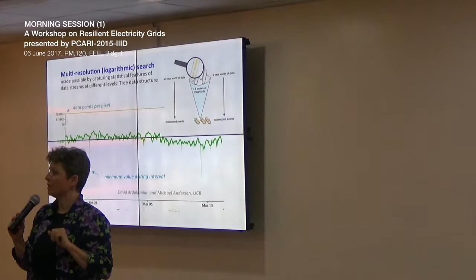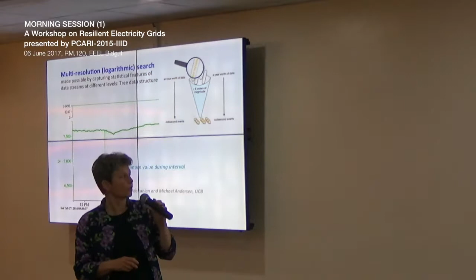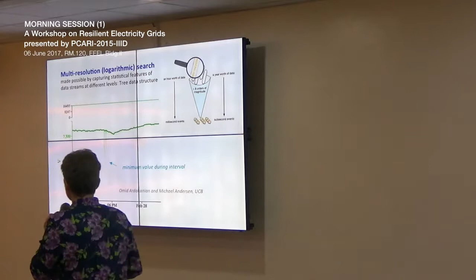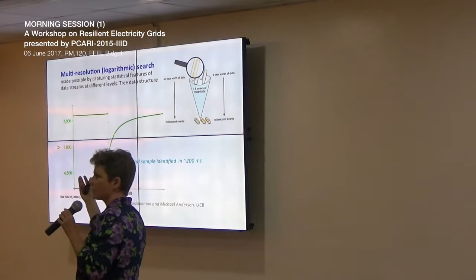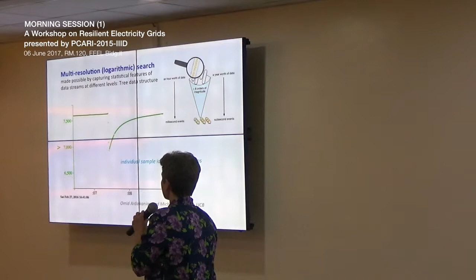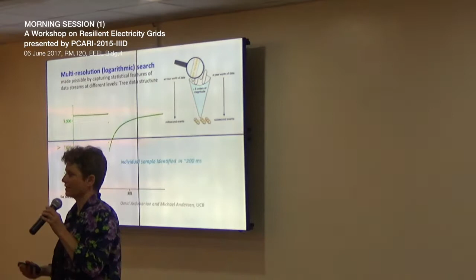We can find voltage sags without digging in too much deeper, but I can then zoom in and say, okay, the voltage sag on February 27th was actually there, and now we're down to 16,000 data points per pixel. I can zoom in further, either by machine or just as a human visually, and find exactly when this voltage sag happened. By machine this took a fifth of a second to do.